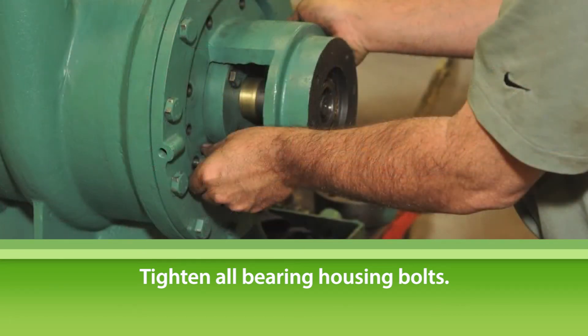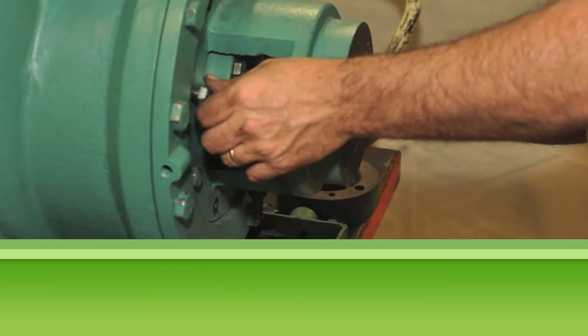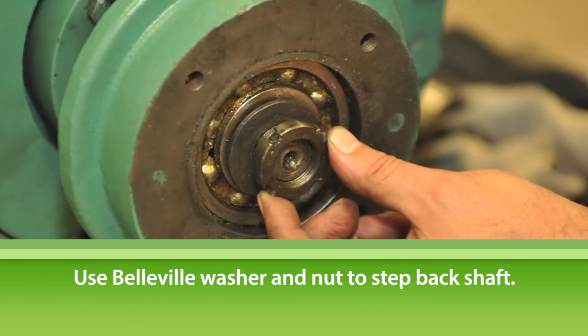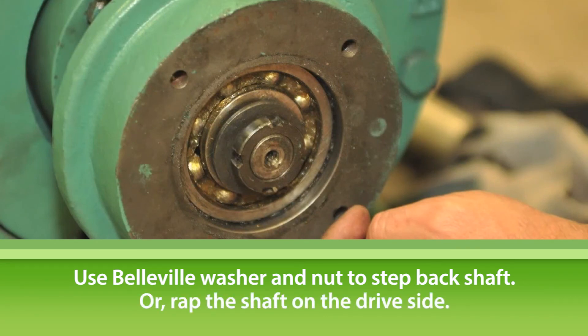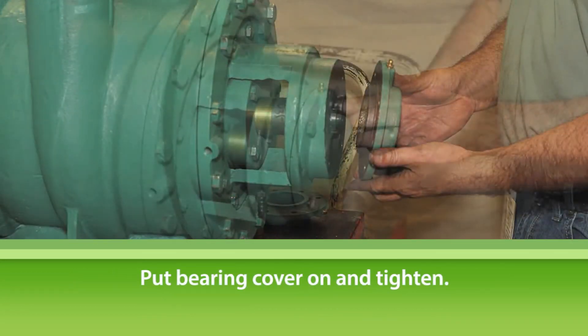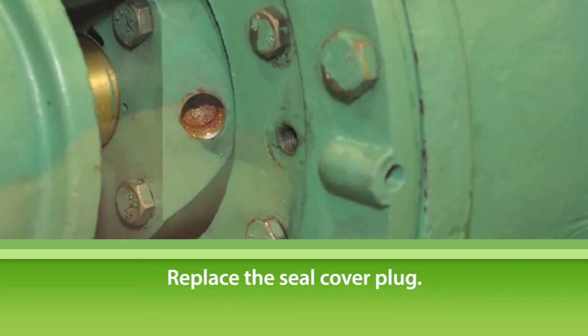In some cases, the shaft will move forward when installing the bearing housing. If that happens, using the Belleville washer and retaining nut, draw the shaft step back so that it's flush with the inner bearing race, or rap on the shaft from the drive side until the shaft end is flush to the inner bearing race. Put the bearing cover in place and tighten it down. Replace the seal cover plug.